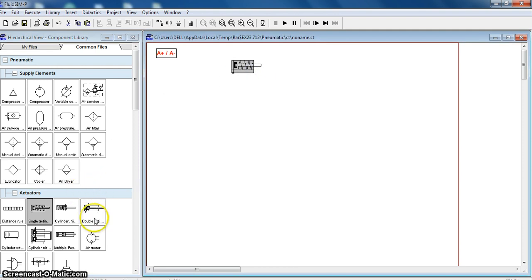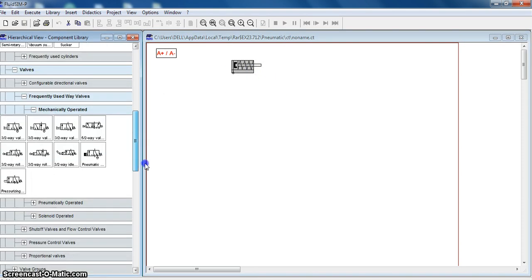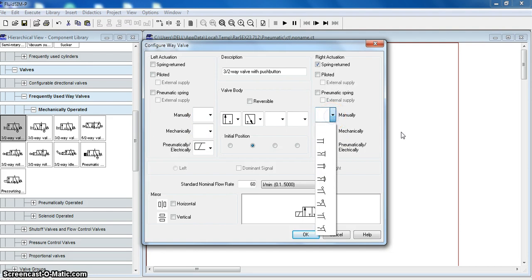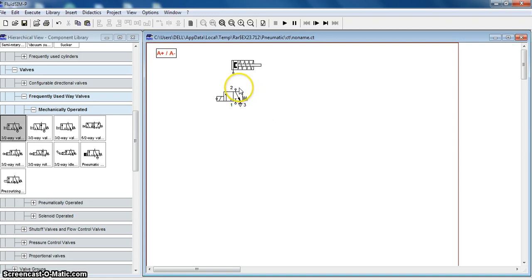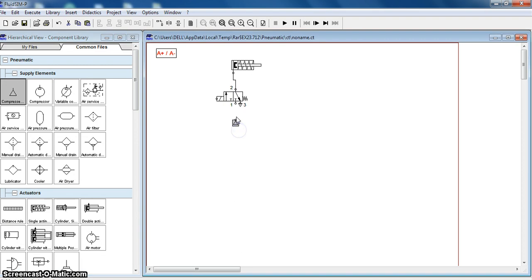We will fire it by using a 3/2 valve. This 3/2 valve should be operated by using a solenoid, and from this end it should be spring return — it is already spring return. Let us connect this end to the cap end of the cylinder. We will use a compressor to give the supply connection. Let us name this solenoid as Y1.